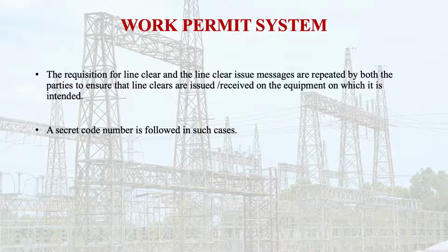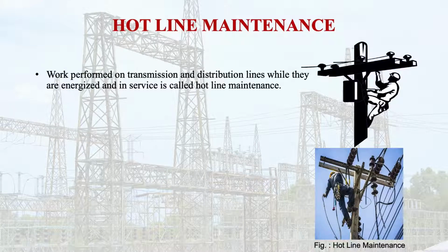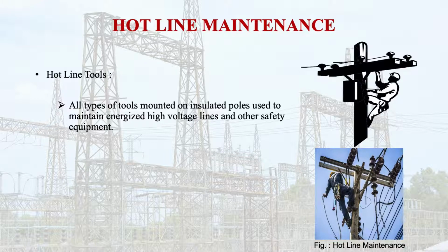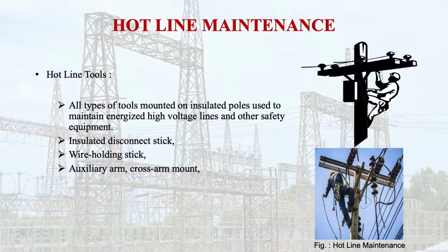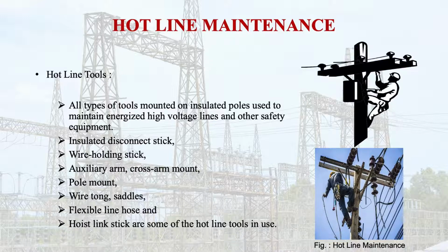Now, we will see what hotline maintenance is. The work performed on transmission and distribution lines while they are energized and in service is called hotline maintenance. All types of tools mounted on insulated poles are used to maintain energized high voltage lines, along with other safety equipment. These hotline tools include insulated disconnect stick, wire holding stick, auxiliary arm, cross arm mount, pole mount, wire tong, saddles, flexible line hose and hoist link stick.